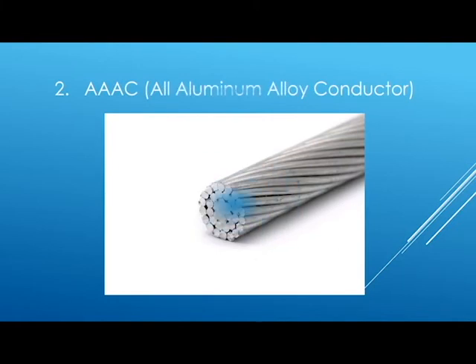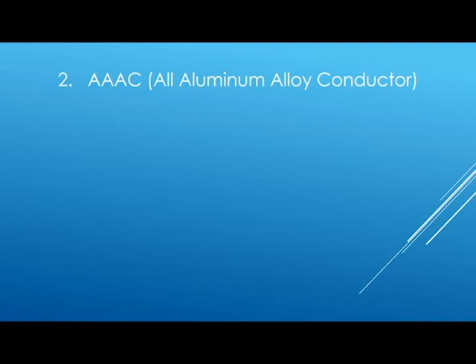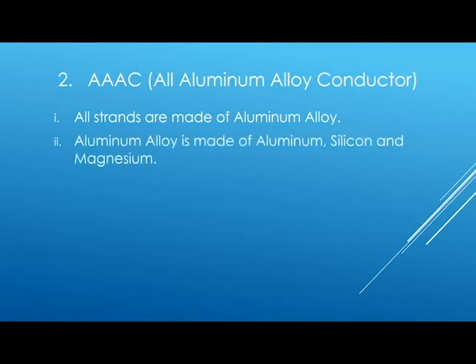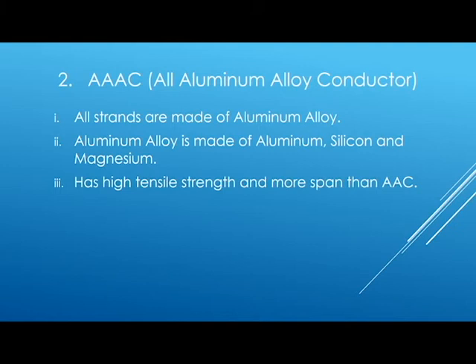Next is the AAAC conductor. AAAC stands for All Aluminum Alloy Conductor. In AAAC, all the strands are made of aluminum alloy. Aluminum alloy is basically a mixture of three elements: aluminum, silicon, and magnesium. AAAC conductor has high tensile strength and longer span than AAC conductor.